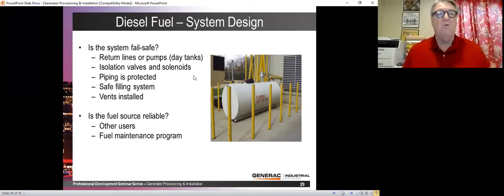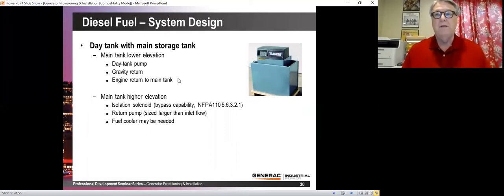The system, you can read some of the things in there that are necessary whenever you have an outdoor tank. An outdoor tank gets less reliable because now you've got to have fuel pumps and fuel level systems and so on, and everything can fail. This is a day tank. Inside, this would have a main tank mounted outside.